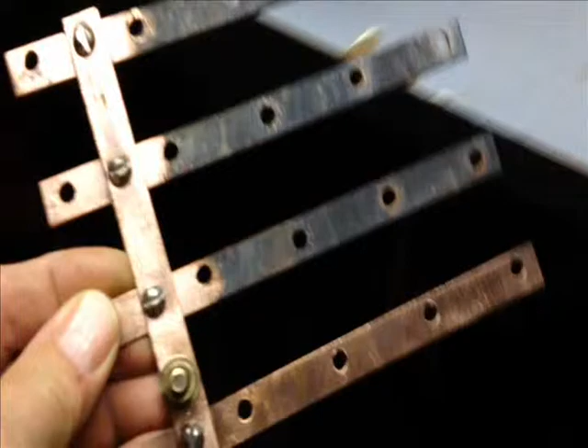Folks, George Shively back with you here. I wanted to show you something we ran into on the DC electrical panel. The horn wasn't working, and I traced that back to the electrical panel. I thought initially it might just be a bad horn, but as it turned out, the DC electrical panel where all the breakers was pretty corroded. If you look at this here, you can tell the bus bars that connect all of the hot sides of the circuit breakers were just corroded, black, green, real ugly stuff going on.